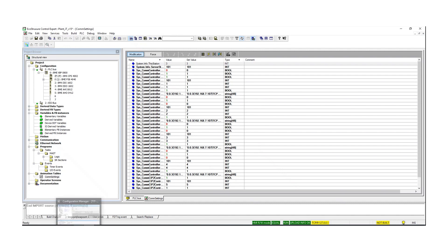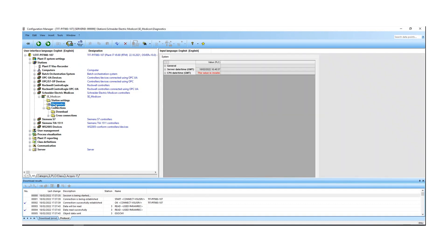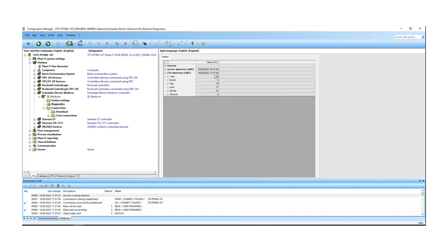That was what we had to do in Control Expert. Now we can check if the connection is established. Go back to the configuration manager, select the Modicon PLC, and open the diagnostic field. We can see the time from the PLC was updated, confirming the communication between the PLC and the plant IT server is working.